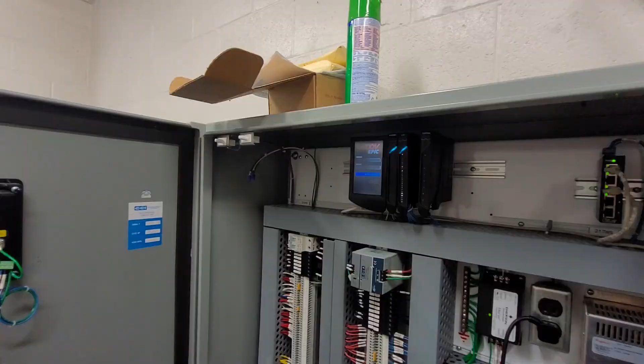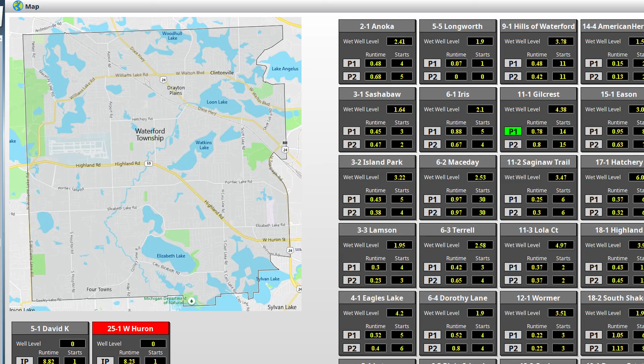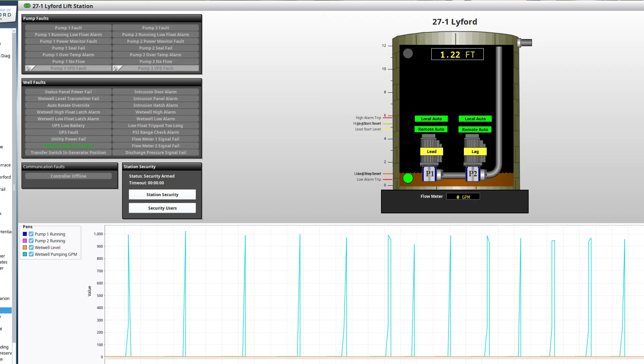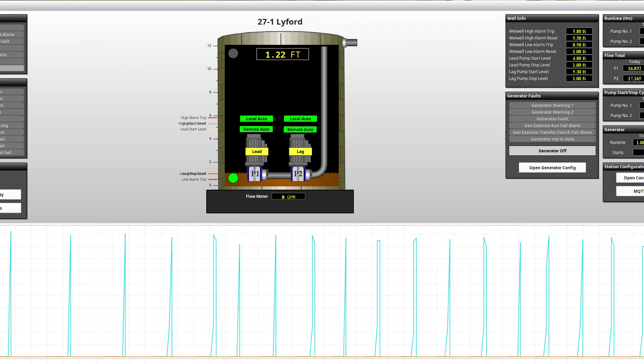Originally they relied on a polling scheme, which would poll each individual site one at a time to collect the data. But given that there are so many sites, it would sometimes take 3 to 4 minutes between each site to collect running status. A lift station can run completely in that 3 to 4 minutes, so sometimes the operators would miss entire cycles that had gone by.